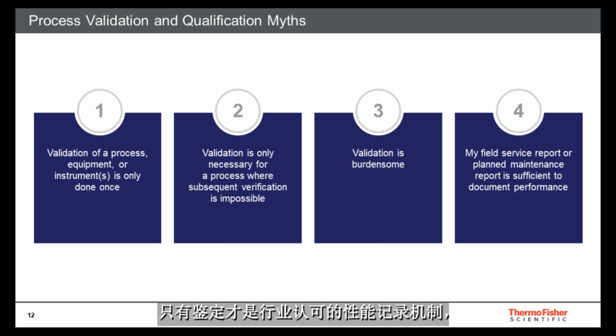Only a qualification is the industry-accepted mechanism to document performance, as called out in the Global Harmonization Task Force, the International Medical Device Regulators Forum, and FDA Medical Device Quality Systems Regulations guidance documents we spoke about in the beginning of the webinar.